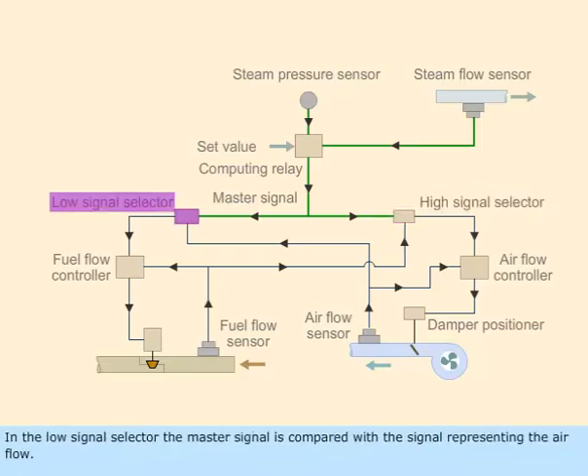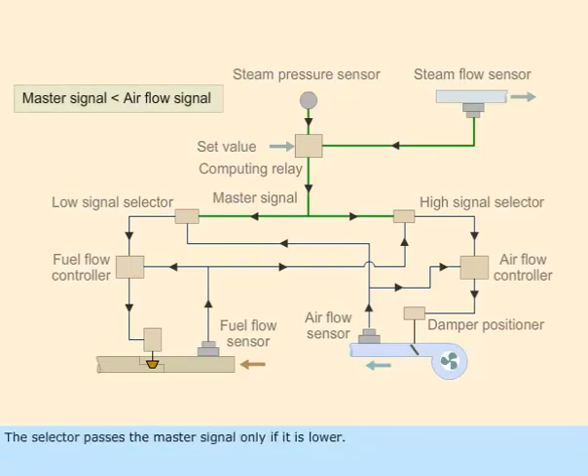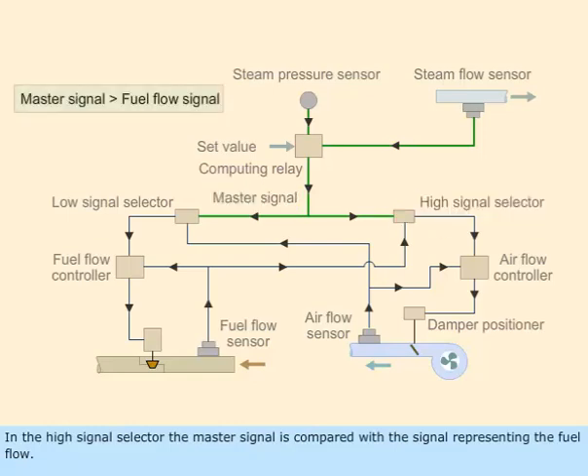In the low signal selector, the master signal is compared with the signal representing the air flow. The selector passes the master signal only if it is lower. In the high signal selector, the master signal is compared with the signal representing the fuel flow.